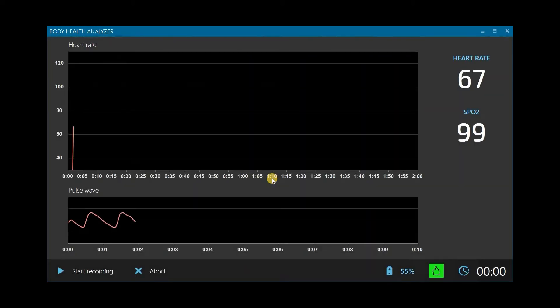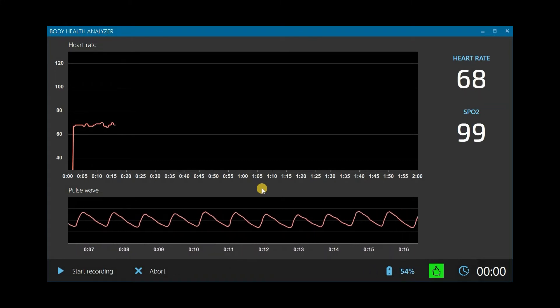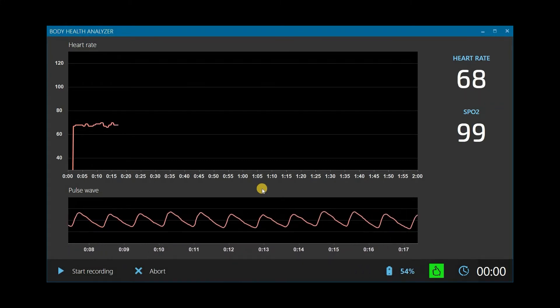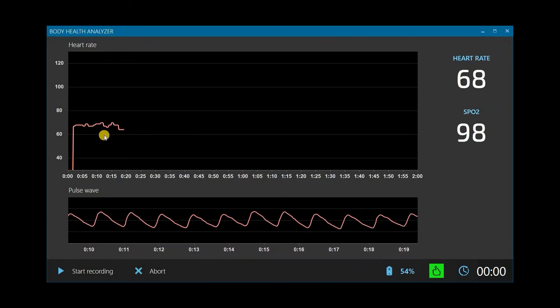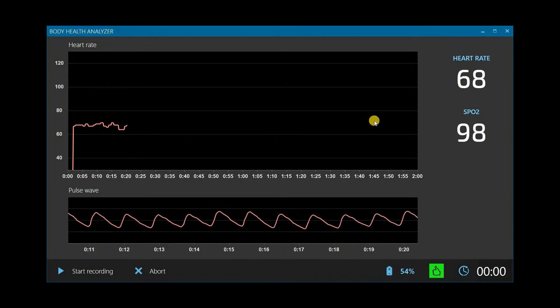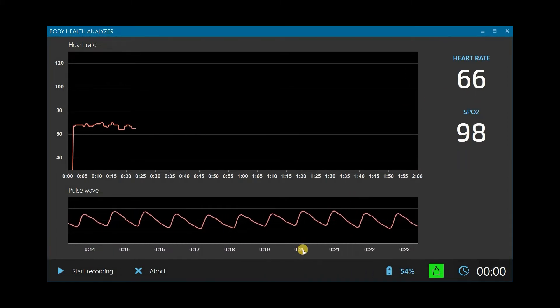Now we see a live test screen. The bottom graph shows a pulse signal. If the sensor is placed correctly, the signal shows smooth periodic waves. The top graph shows the heart rate changes. Instantaneous heart rate and SpO2 values are displayed on the right.